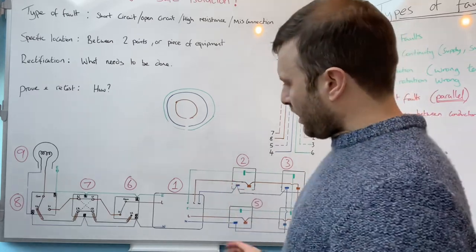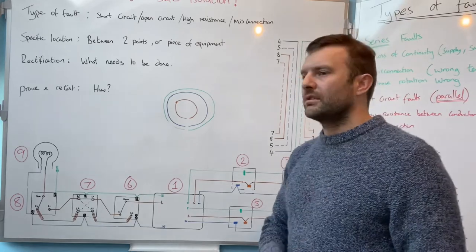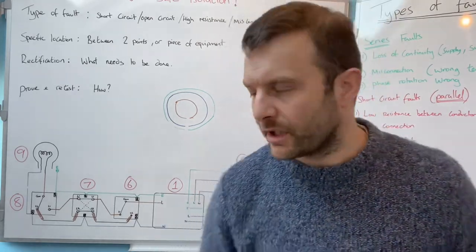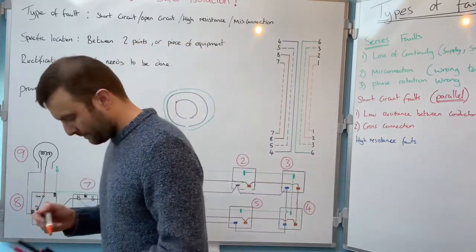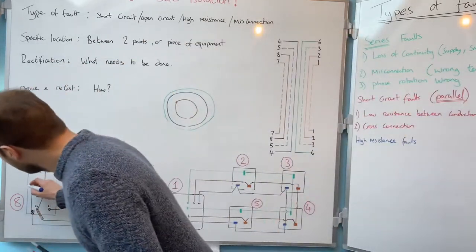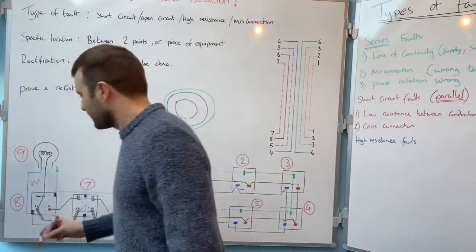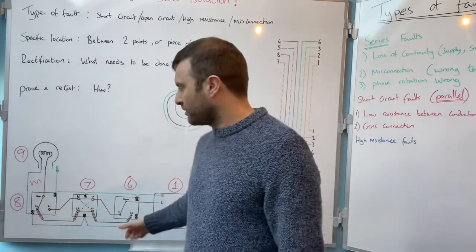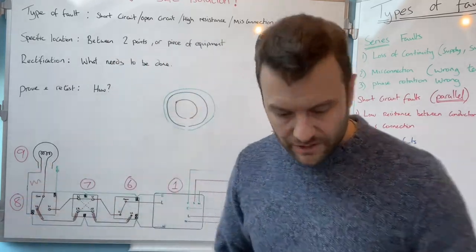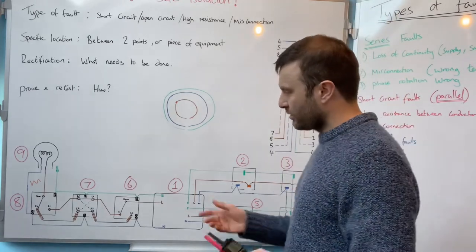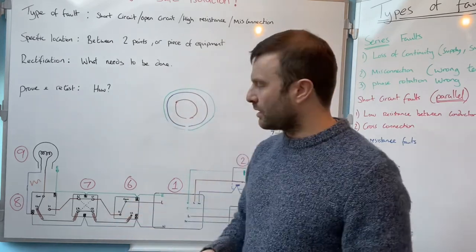Okay, over here I've now got a lighting circuit. So in this instance, again, if the fault was something's tripping out, well, then I've got a short circuit. So whether that's between live to neutral or live to earth, could be up here. Just notice there's a little missing there. So if I had a fault here, every time I flick the switch on, the light trips out. Well, I've got continuity between live and neutral. So what I would then do is test with the switch on, obviously, between live and neutral. And if I've got continuity, I've got a fault.